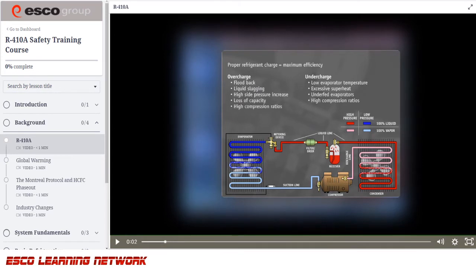An overcharge can cause the metering device to overfeed the evaporator and back up liquid refrigerant in the condenser. These conditions could create floodback, liquid slugging, high side pressure increase, loss of capacity, and high compression ratios.